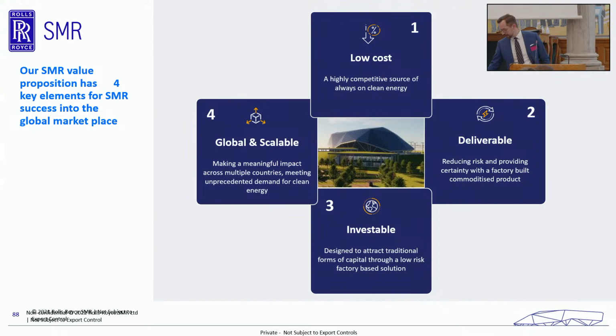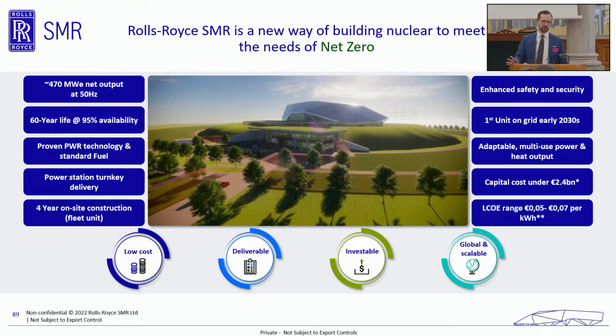In terms of some basic facts from the Rolls-Royce reactor, thanks again, by the way, Christian, for nodding in terms of delivery capability. It's the largest of the SMRs, 470 megawatts. Two reasons behind this. We realized that if we increase the reactor size from about 300, which is a popular size, to 470, you get an increased cost, but compared to getting 50% more power, the cost is very minimal. Second is that the physical size of the reactor remains road transportable in all of Europe, which was a design limitation for us, that it needs to be delivered on a standard truck, or more or less a standard truck, in all of Europe, instead of requiring anything specialized.